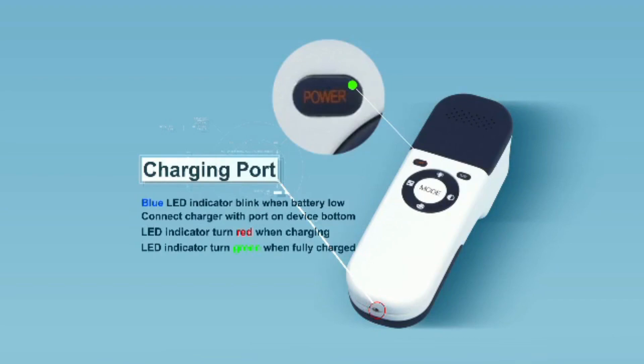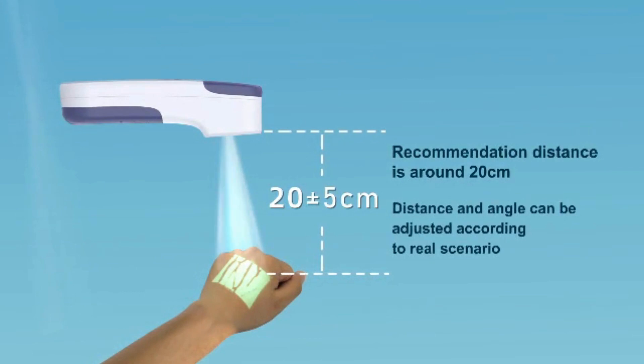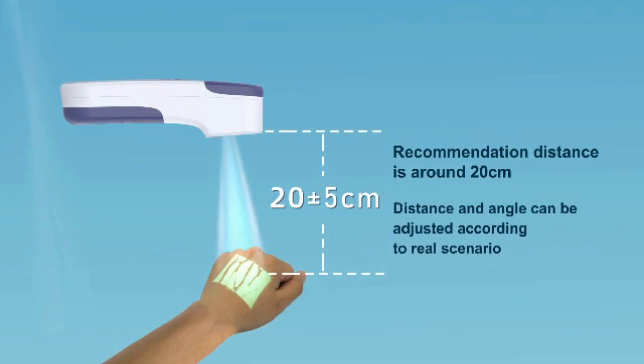To get a good vein image of the patient, keep the distance between VeinFinder and skin at around 20cm. This distance can be adjusted appropriately according to real scenario to ensure the projected image is clear.